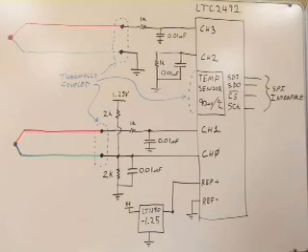The 2492 has an onboard temperature sensor that gives about a 90 microvolt per degree C signal, so this can be used to calculate the cold junction voltage in software.